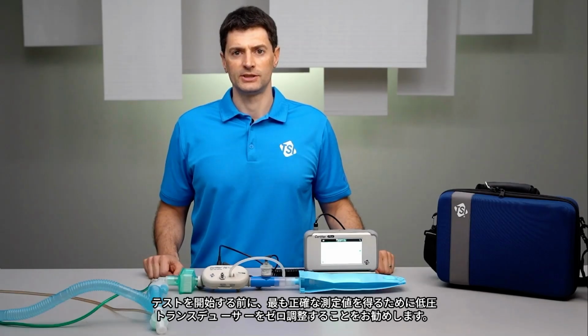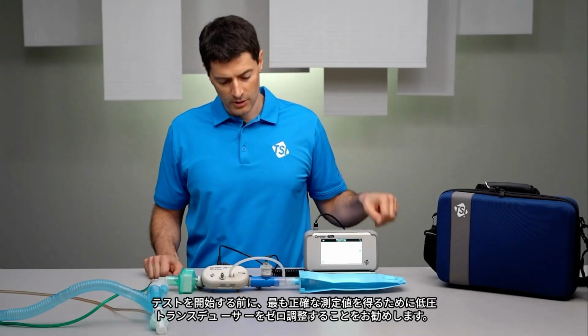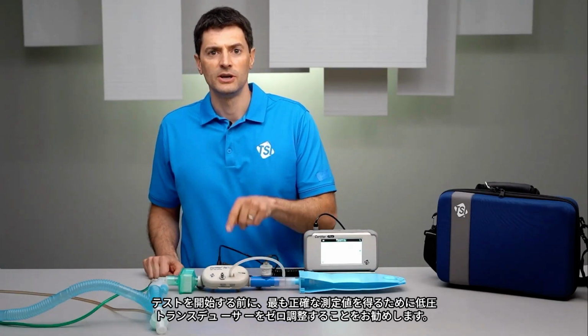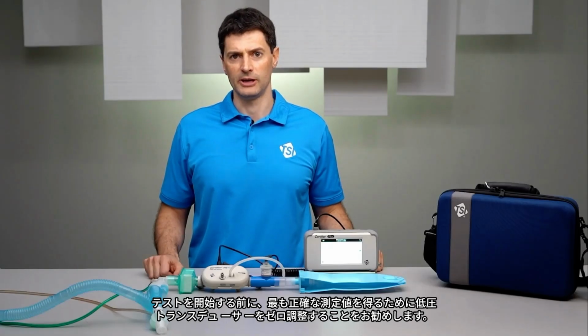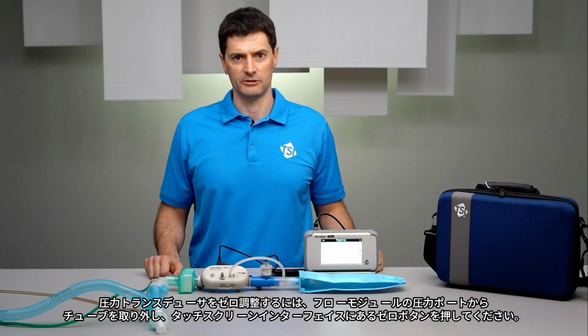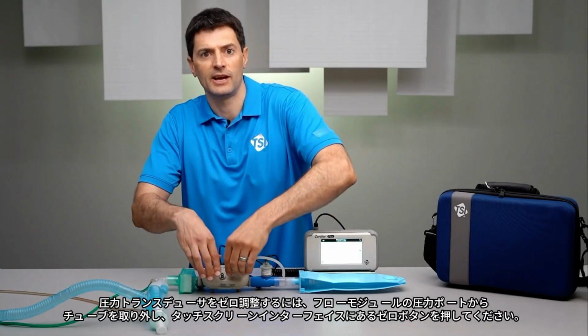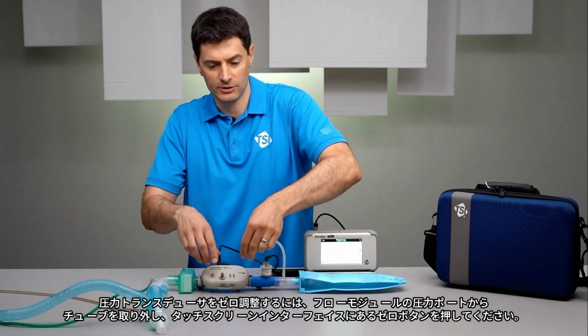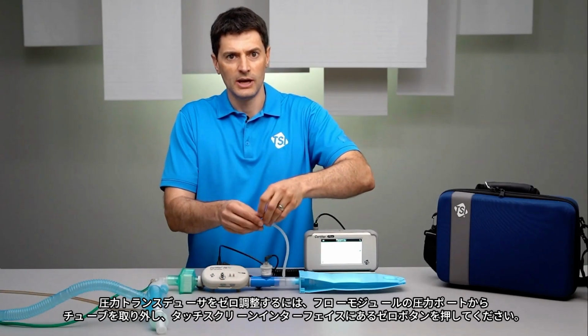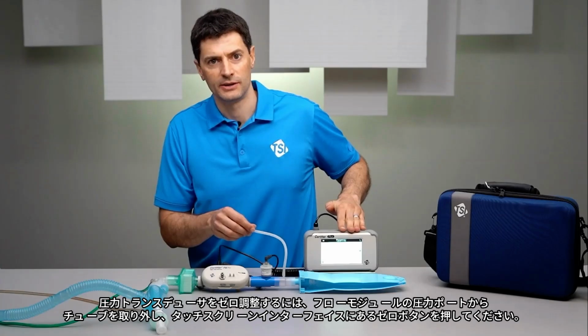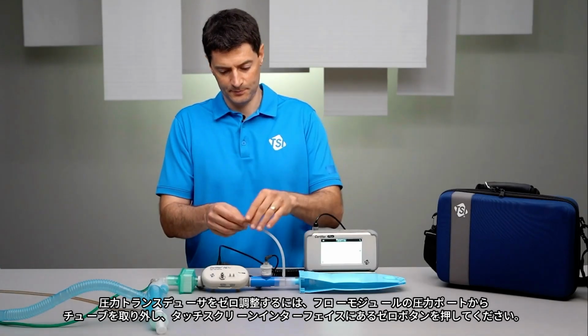Before you start testing, it's recommended to zero the low pressure transducer to ensure the most accurate readings. To zero the pressure transducers, disconnect any tubing from the pressure ports located on the flow module and then press the 0 button that's on the touchscreen interface.